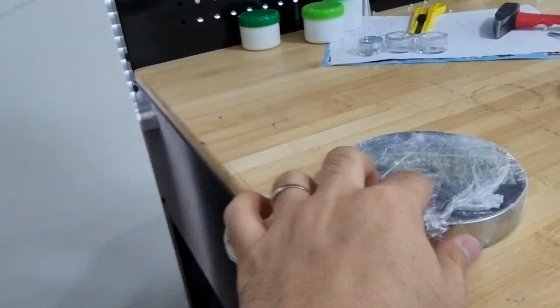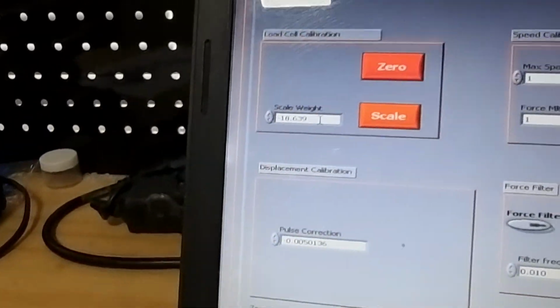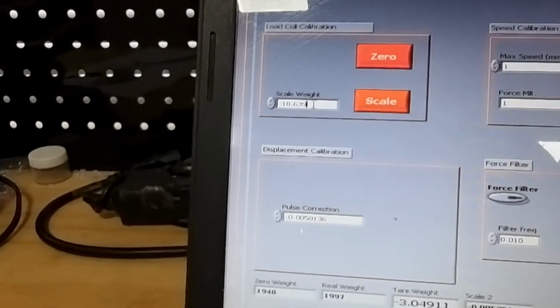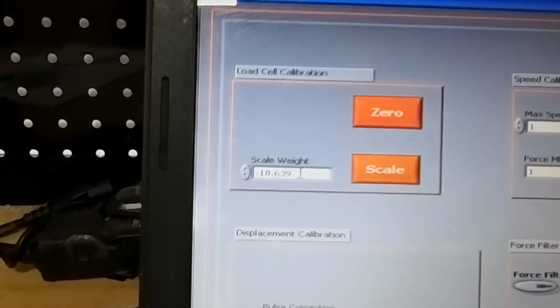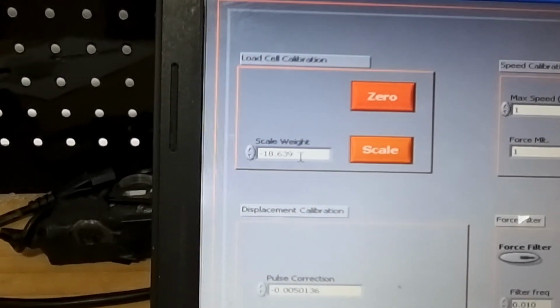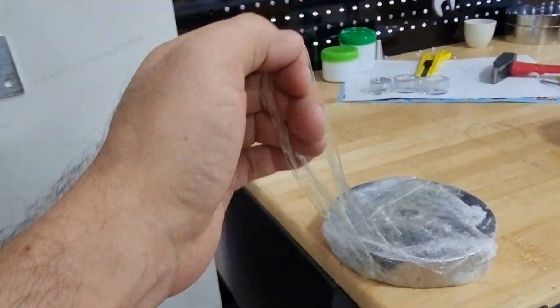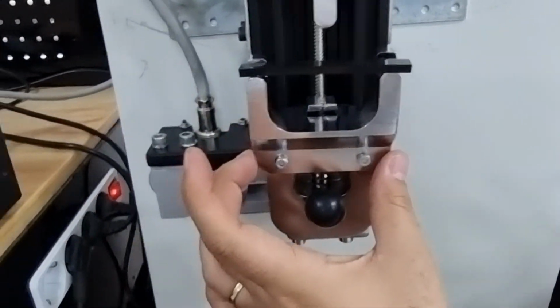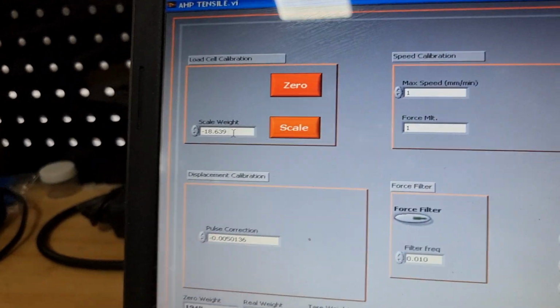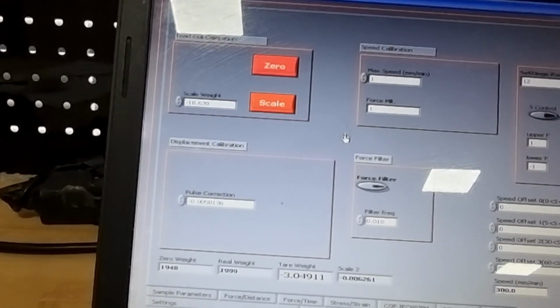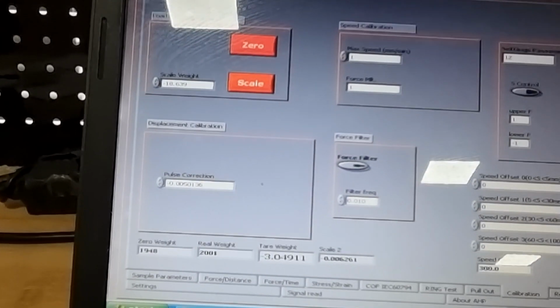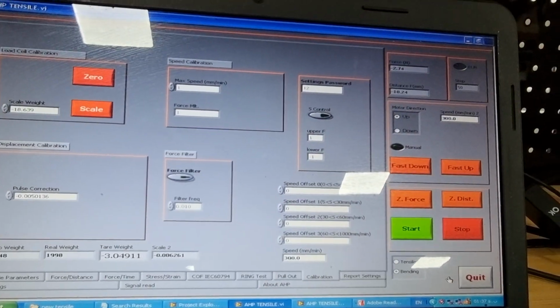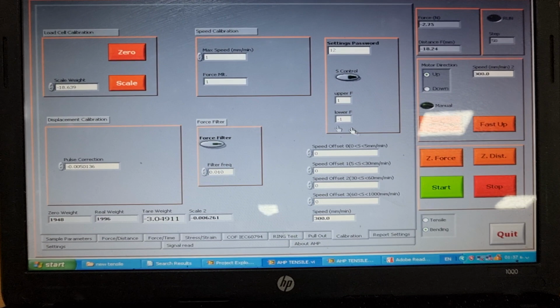This is 1.9 kilogram, meaning 18.639 Newton. You will put the value here in terms of Newton. And after hanging this sample piece from here, you will click on scale, and the load cell will be calibrated with a definite weight, and that's all. After clicking on scale, you need to click on quit here, and the software is already calibrated for the load.